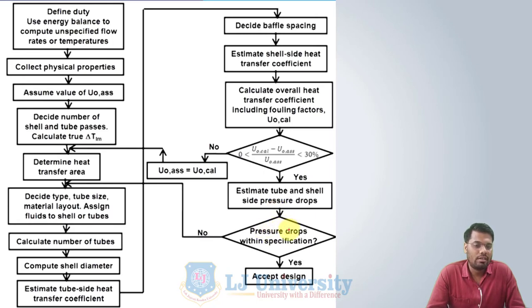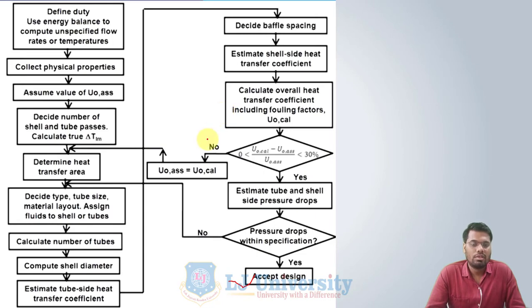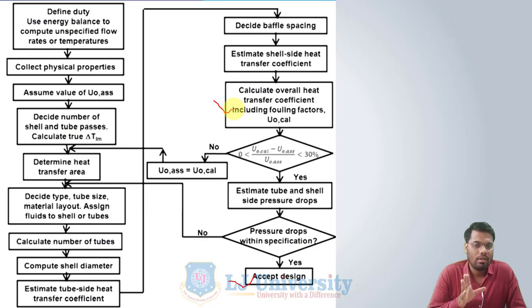If the pressure drop of shell side and tube side is within the permissible limit, the design is accepted. If the calculated pressure drop is not within the permissible limit according to customer or design requirements, we have to repeat the design steps — changing the tube size, tube diameter, or tube material — and recalculate all steps to get the pressure within the limit. These are the design steps for shell and tube heat exchanger design by Kern's method. We can also use the Bell-Delaware method to calculate the overall heat transfer coefficient at the shell side, while for the tube side, the method remains the same.